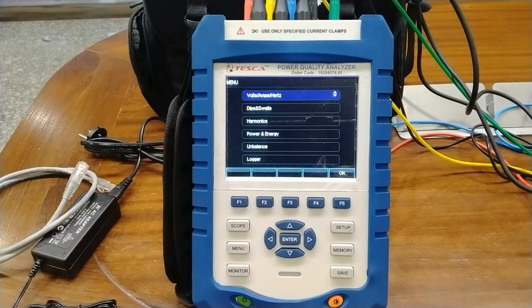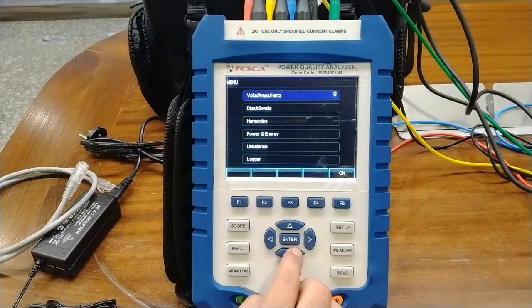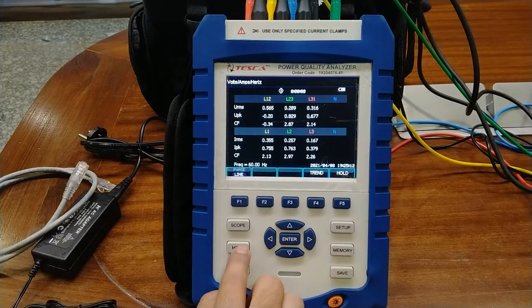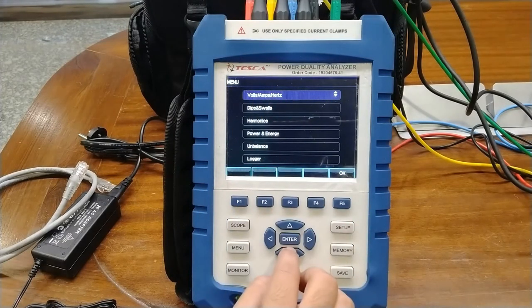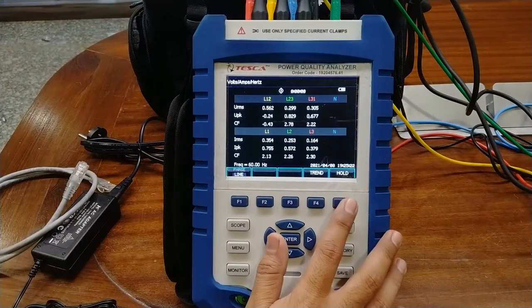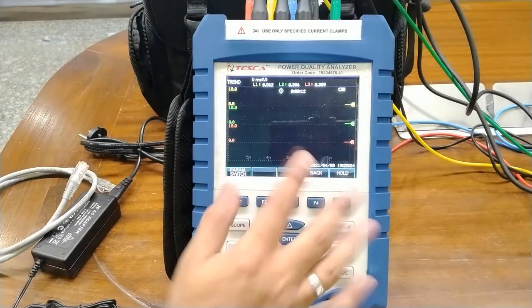In the menu section, different options are provided. You can select measurements: volts, ampere and hertz; dips and swells; harmonics; power energy; unbalance; and logger. Logger is for data logging of all parameters. We have selected the volts and ampere hertz section and pressed OK. In the tabular form we have the numerical values of voltage, current, frequency, and crest factor. When you press F4 you can go to the trend section — all L1, L2 and L3 voltage VRMS values are provided and we can see the trends.